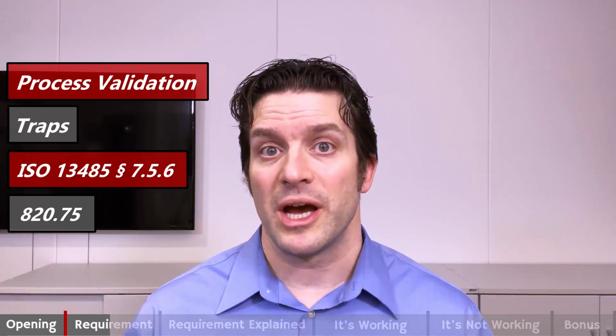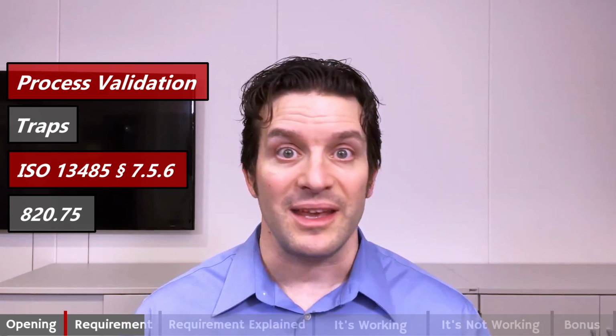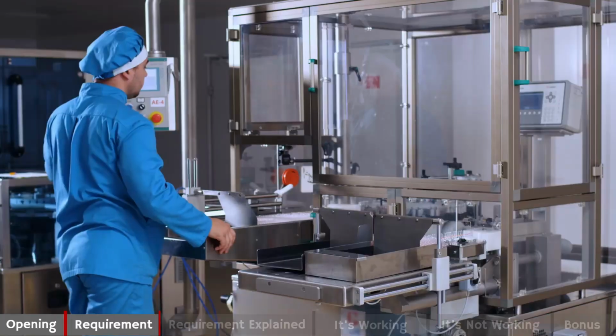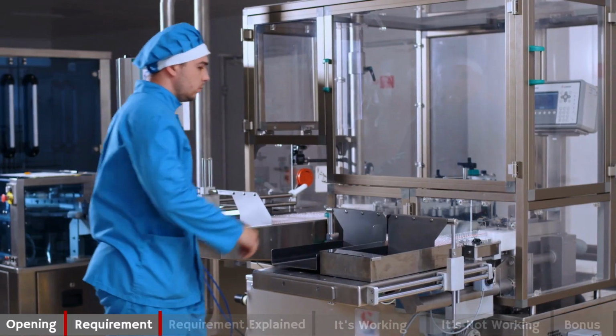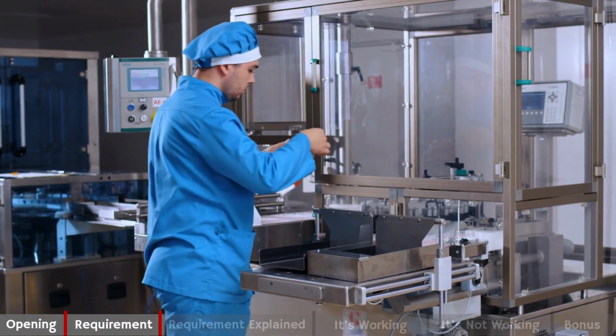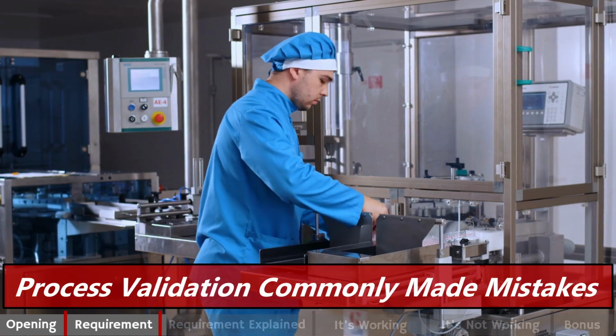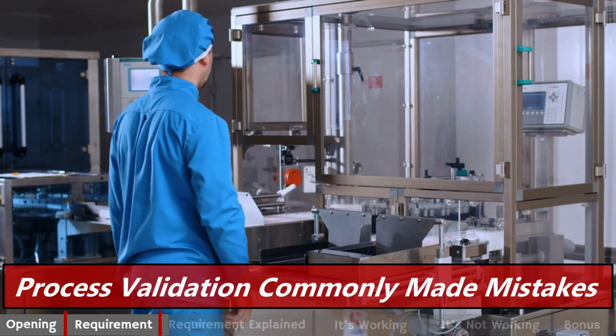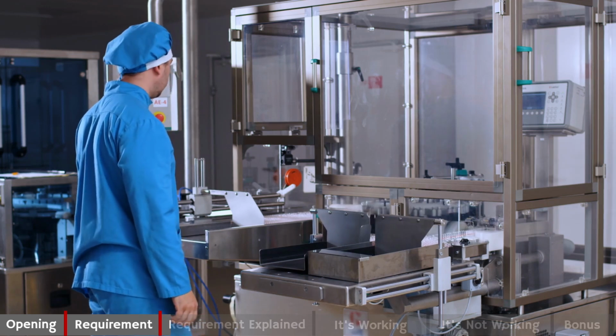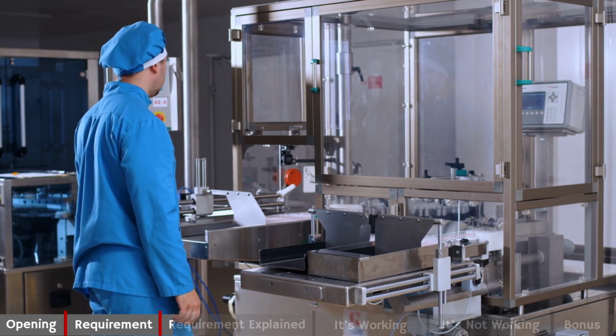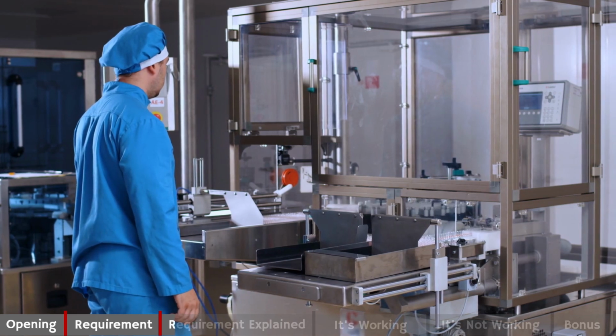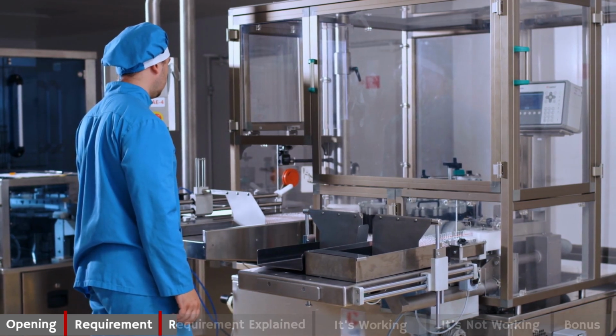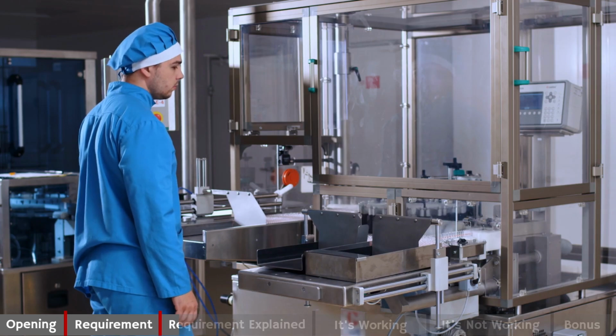Our topic, process validation traps, links directly to the process validation requirements, which come from 13485 section 7.5.6 and 820.75. Process validation traps in 5 words: process validation commonly made mistakes. As you look across the industry, when it comes to process validation, there are a number of mistakes that repeatedly happen time after time after time across the industry. Here, we're going to talk about 6 of those.